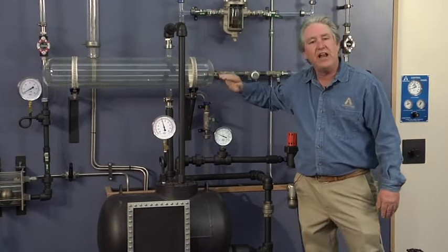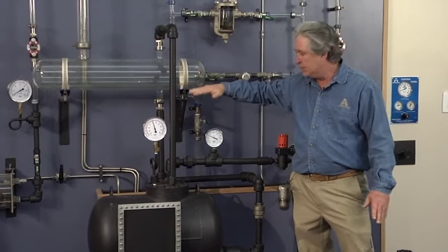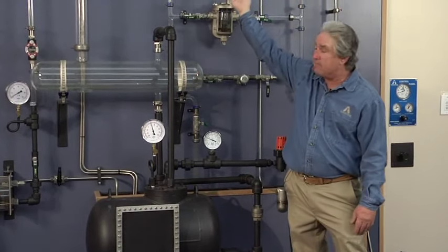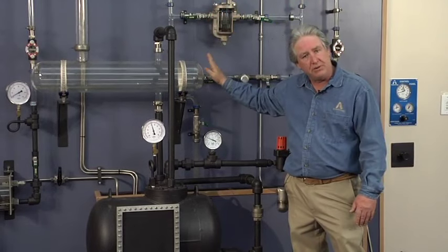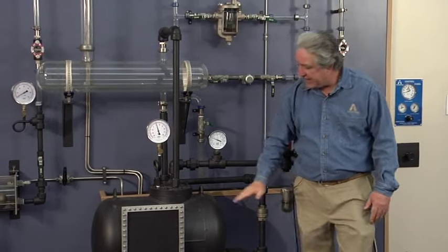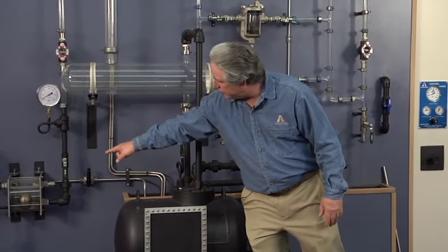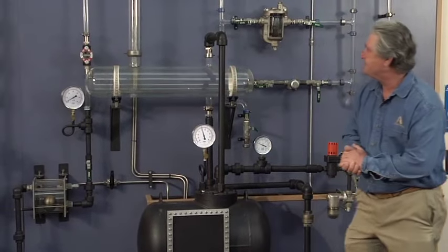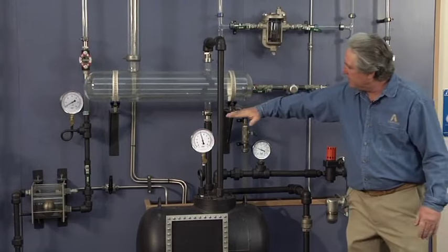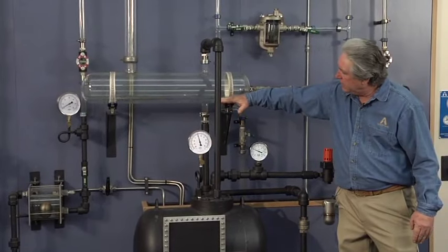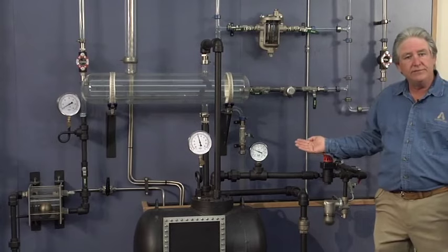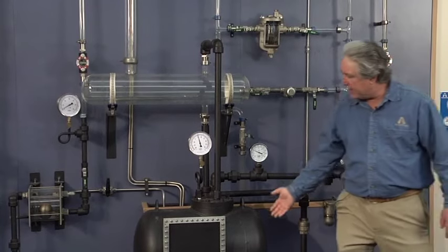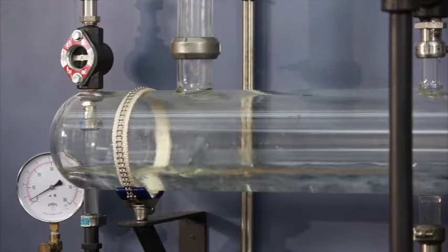We have to have an adequate reservoir to take the amount of liquid that we condense in the exchanger and allow it to gather someplace while the pump is pumping the liquid out through the steam trap. Okay? What you're going to see is the continual raise of level in the glass reservoir piping as we're trying to pump out through the trap and into the return header.